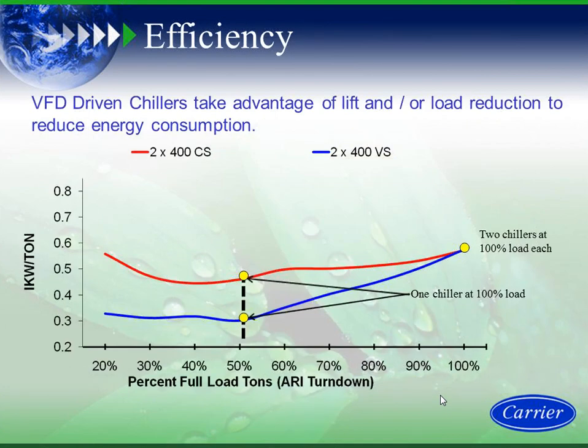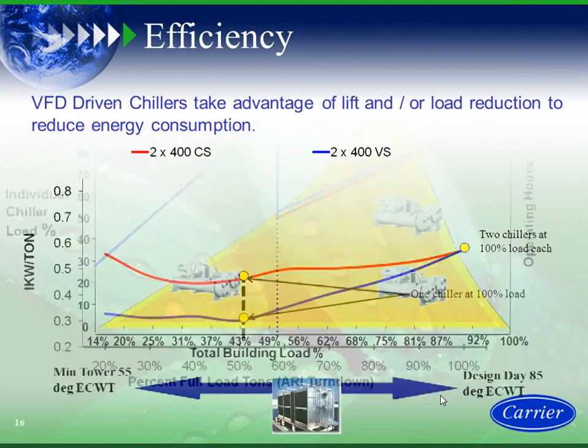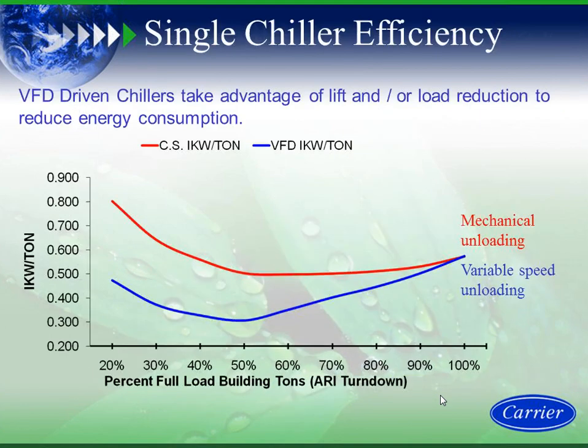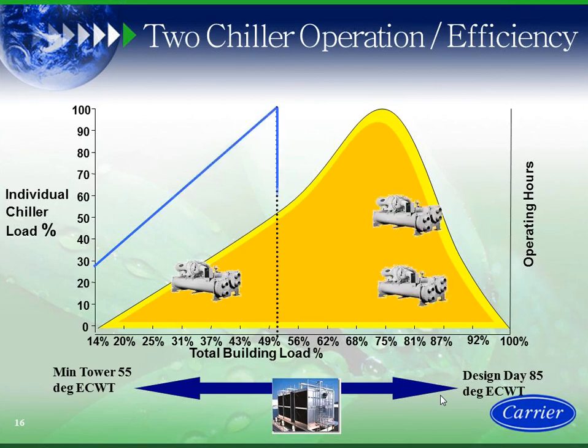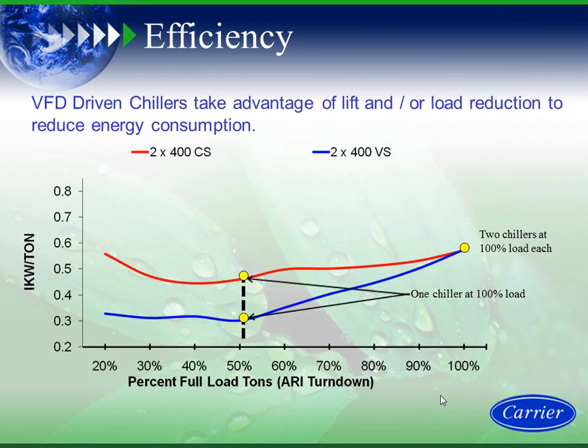Now let's look at those 2 pieces. On the previous slide I said that at the 100% load point, they basically have identical or very close to identical efficiency. How come then, over here at this mid 50% point, where one machine has ramped up to 100% and I'm just about to turn on the second machine, are those numbers different? It's 100% load, but the one with the VFD is less kW per ton.